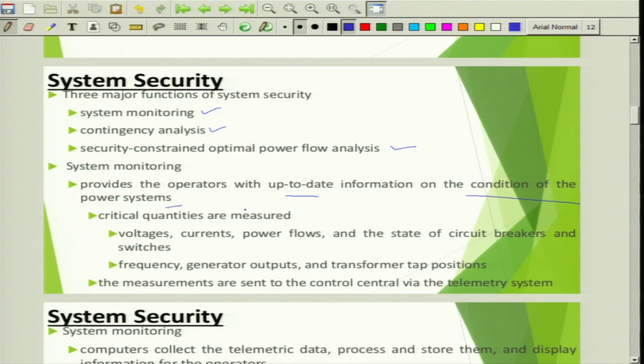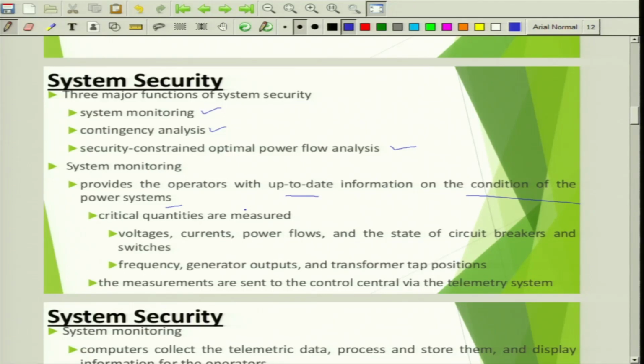There are different monitoring devices placed over the transmission or distribution corridor to help a system operator understand the system state. Like you place PMUs, phasor measuring units, and you keep RTUs and different monitoring devices, CTs, PTs, and all these things are placed such that you get real time information about the system operating conditions. What is the voltage, what is the phase angle, frequency, and all these parameters. These are the critical vital elements required to understand the health of the system, so that you can take appropriate action to ensure system security is retained throughout the operation of the power system.